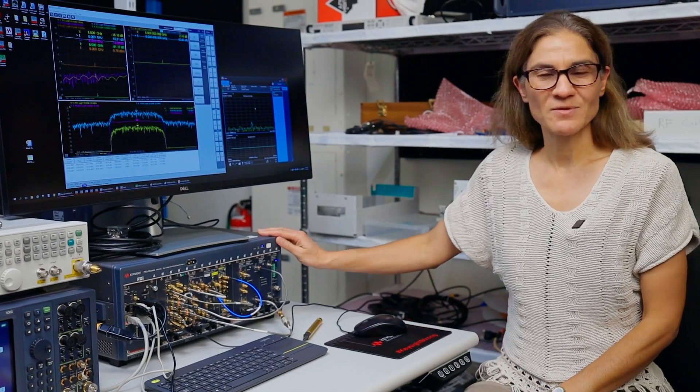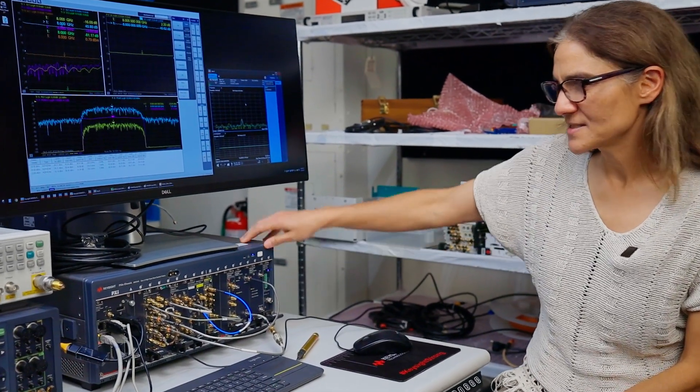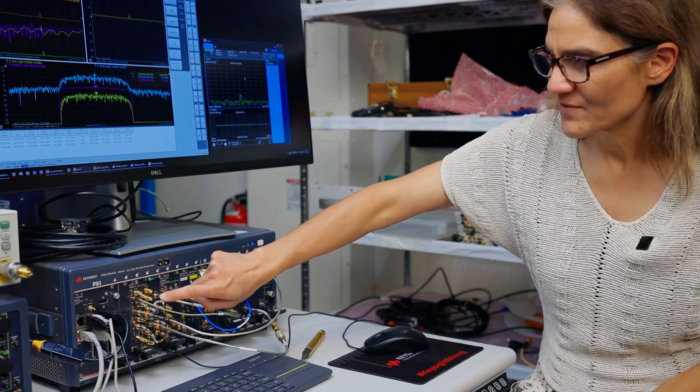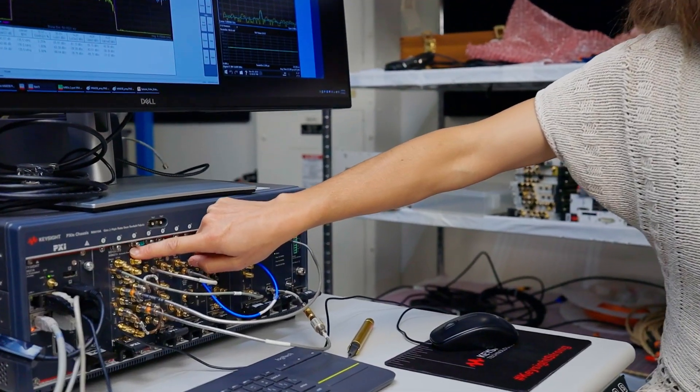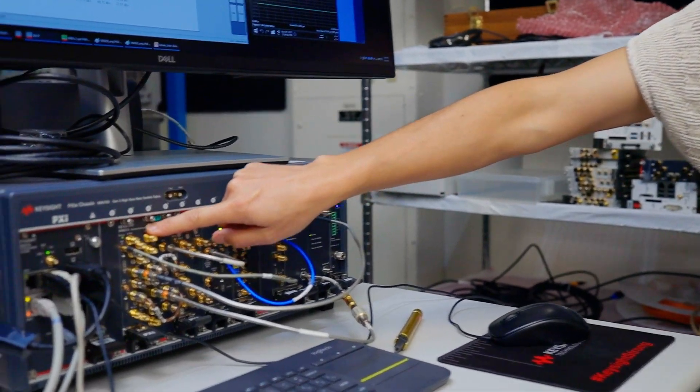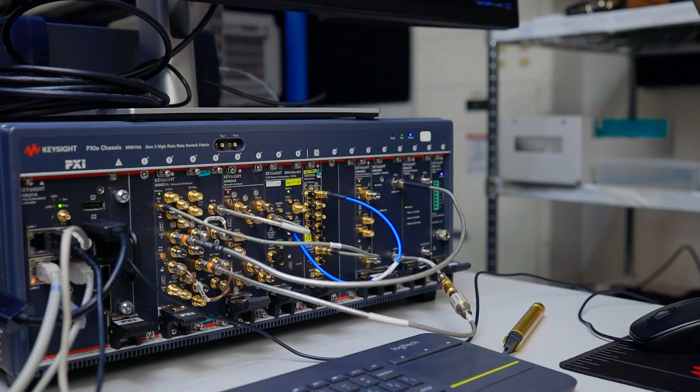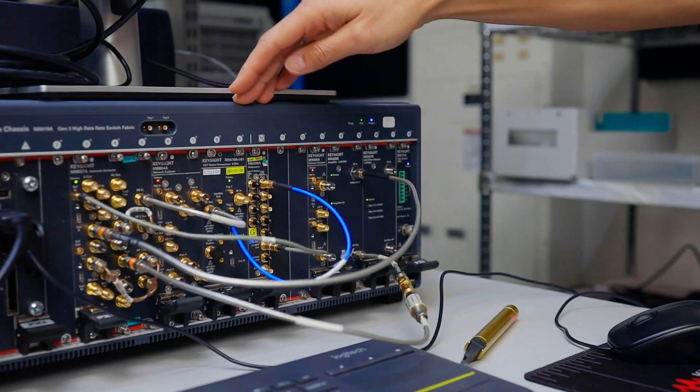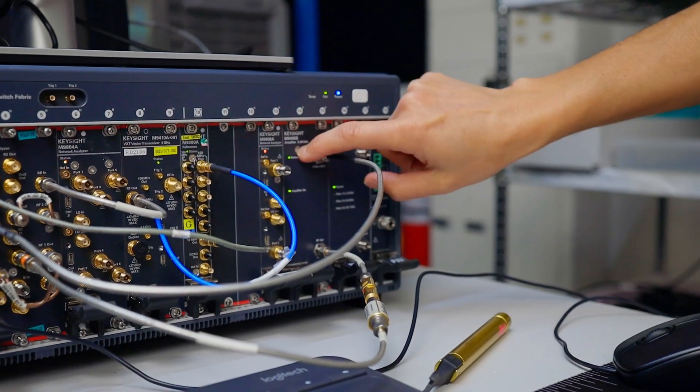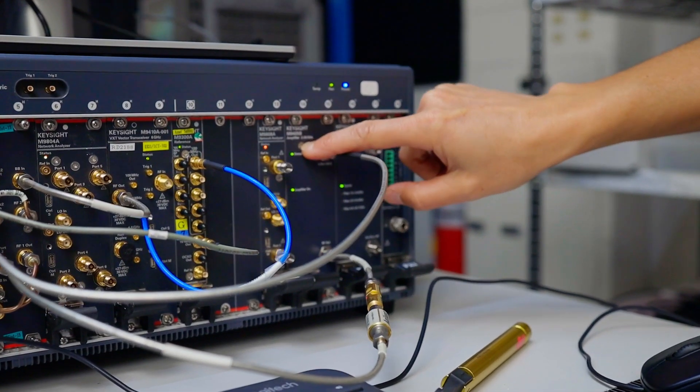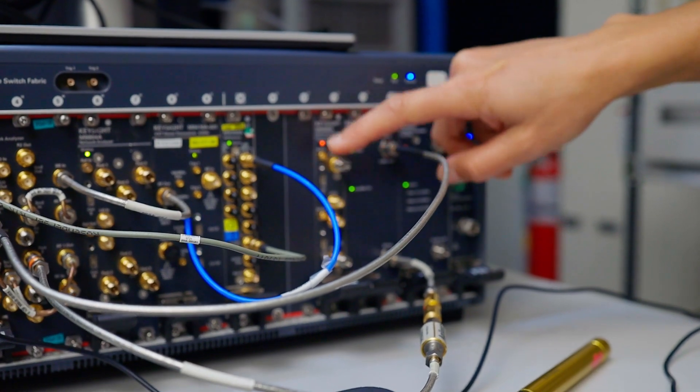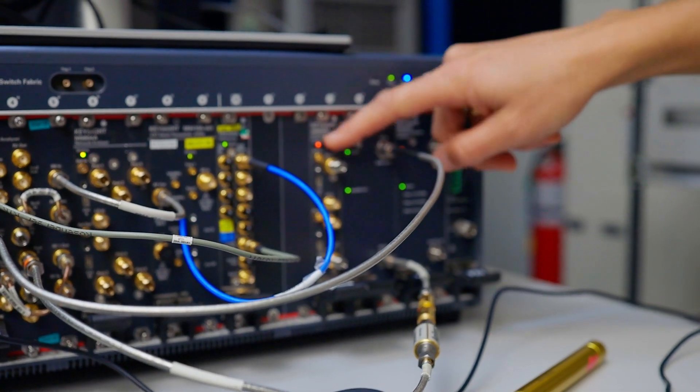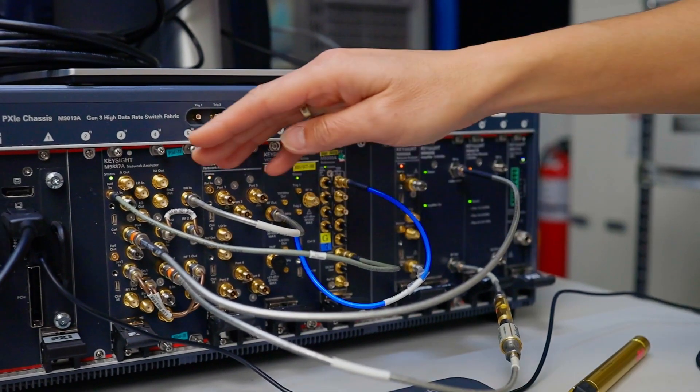Let me show you the hardware and software setup I have here. This is a Pixi chassis. What I have here is the new configurable PXI VNA, 44 gigahertz, two-port module. I have a VXT I'm using as a source. I have this amplifier I'm using as a DUT. And this is a standard PXI VNA. You can see it's only single-slot versus the new one. And Joel's going to be talking about the configurable test set.